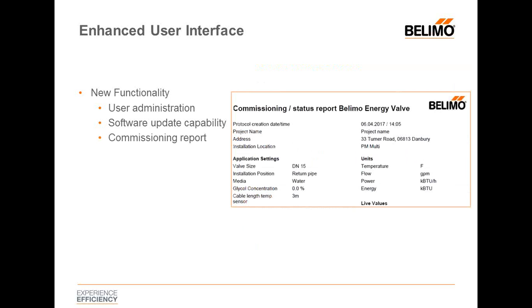We've also added a commissioning report. After the valve has been completely commissioned, there is an ability to generate a PDF that can be provided to the owner confirming the valve has been correctly set up — set at the proper VMAX, the proper installation location in the system — listing all the units it's been set up in. This report can also be rerun if changes to the valve are made based on usage patterns or loads.